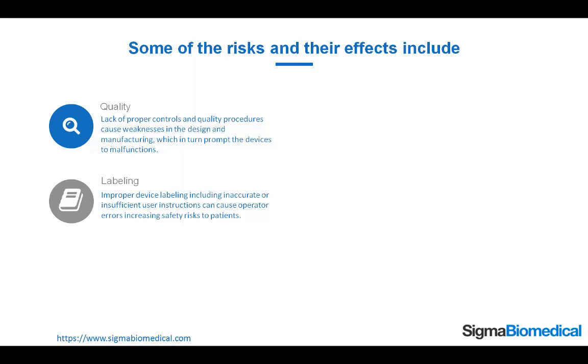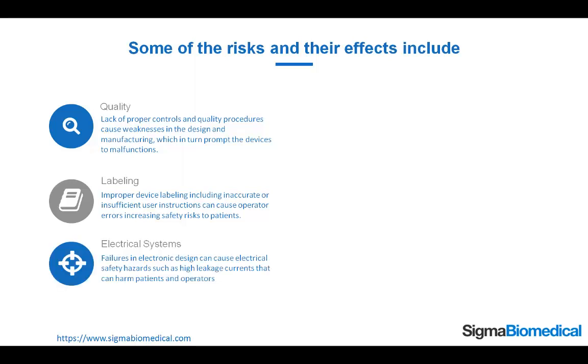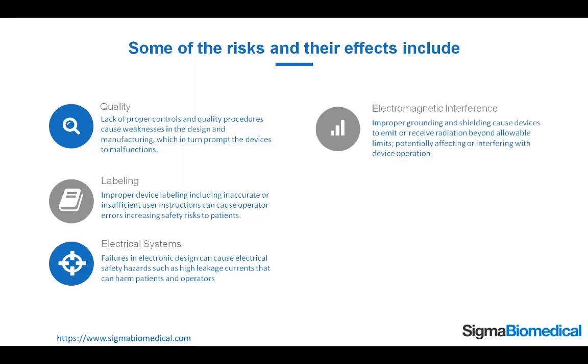Labeling: improper device labeling, including inaccurate or insufficient user instructions, can cause operator errors, increasing safety risks to patients. Electrical systems: failures in electronic design can cause electrical safety hazards such as high leakage currents that can harm patients and operators. Electromagnetic interference: improper grounding and shielding cause devices to emit or receive radiation beyond allowable limits, potentially affecting device operation.